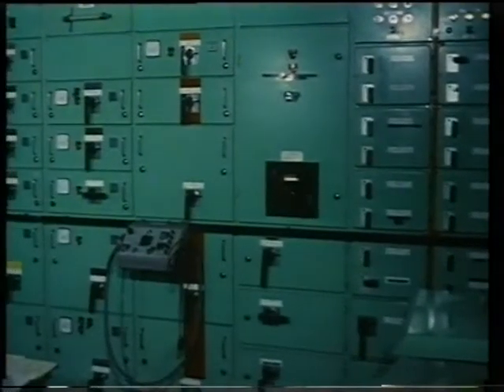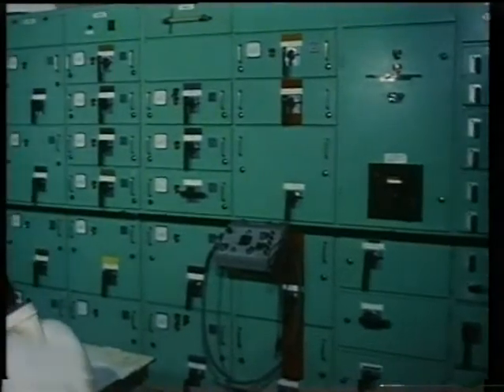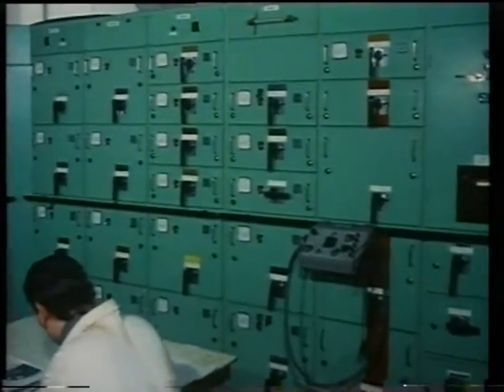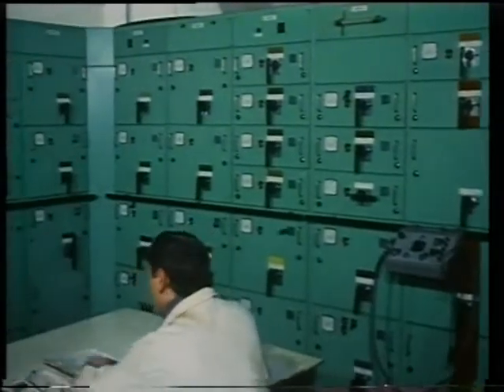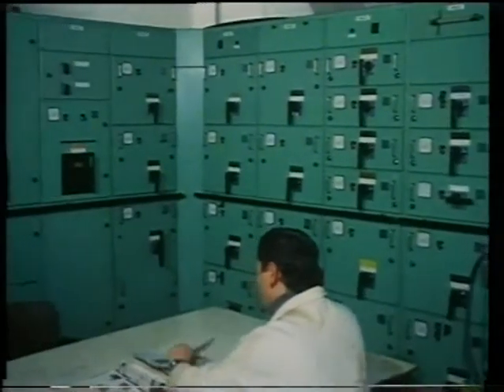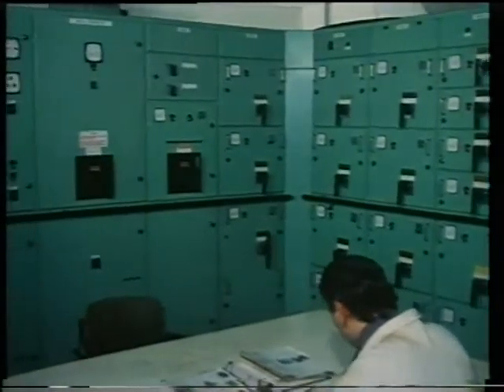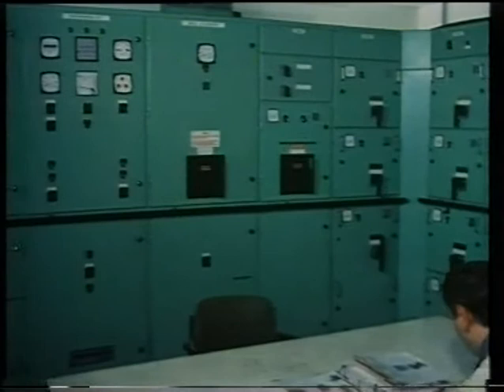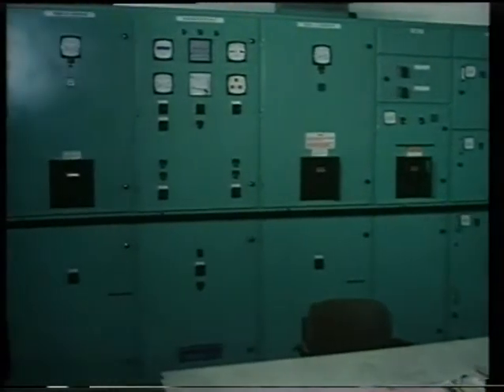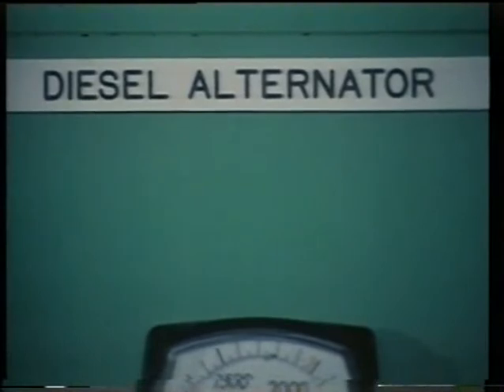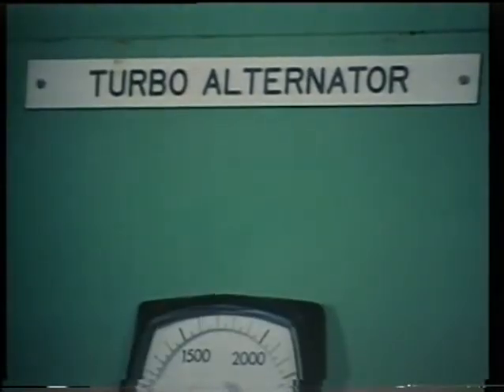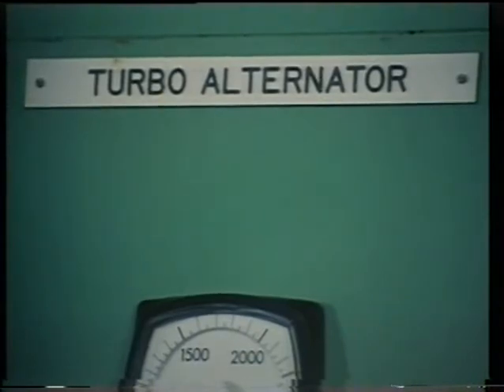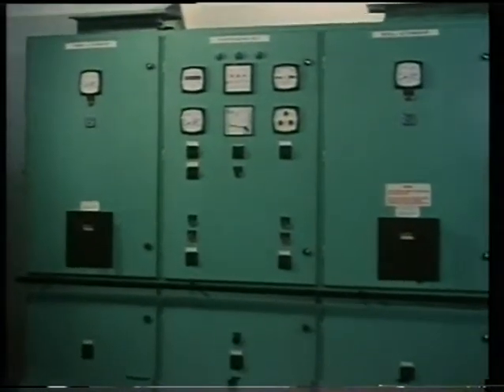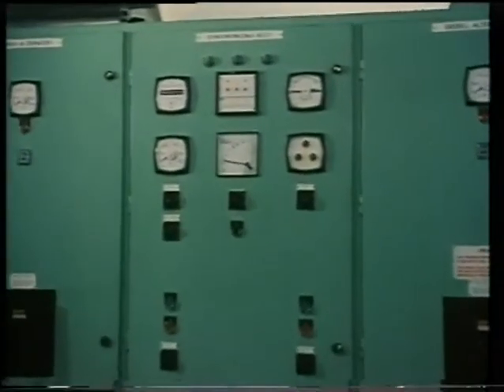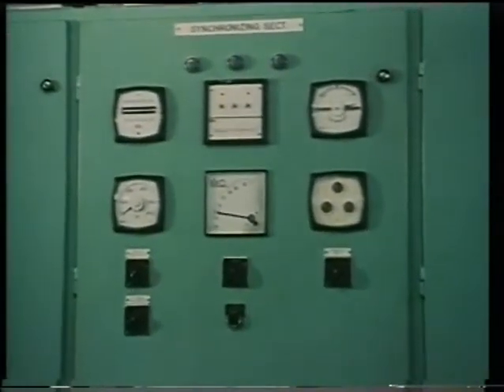And now, the distribution system. The heart of a ship's electrical distribution system is the main switchboard. The generated power is connected to it by the alternator circuit breakers, which connect power to the bus bars. Each alternator has a panel on the switchboard, and the alternators can be connected to the bus bars separately or in parallel. A separate synchronizing panel is located between the alternator panels, which has controls for auto-synchronizing or for manual synchronizing.